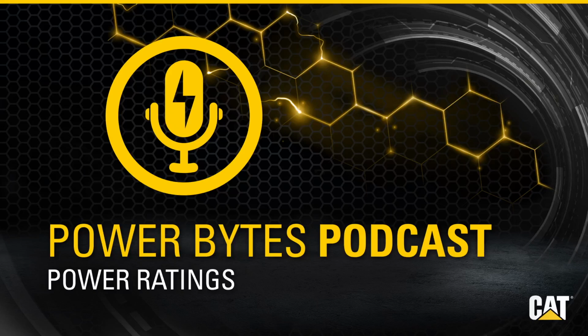Another one then, the most common rating category, is emergency standby, or ESP. Emergency standby allows for a variable load, and much like the prime power, it has a 70% load factor. So we've got some variation over the course of the operation. The big difference with the emergency standby is that within the ISO standard, it only allows for 200 hours per year of operation. So these are applications where you have a reliable grid, but you need to have just something there to provide backup in case of an emergency.